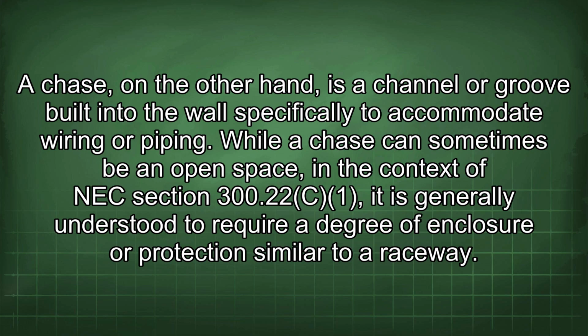A chase, on the other hand, is a channel or groove built into the wall specifically to accommodate wiring or piping. While a chase can sometimes be an open space, in the context of NEC Section 300.22, it is generally understood to require a degree of enclosure or protection similar to a raceway.